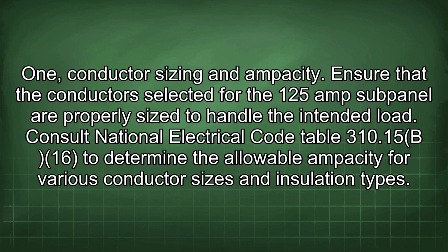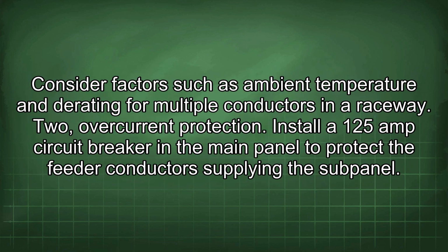1. Conductor sizing and ampacity. Ensure that the conductors selected for the 125 amp subpanel are properly sized to handle the intended load. Consult National Electrical Code Table 310.15(B)(16) to determine the allowable ampacity for various conductor sizes and insulation types. Consider factors such as ambient temperature and derating for multiple conductors in a raceway.